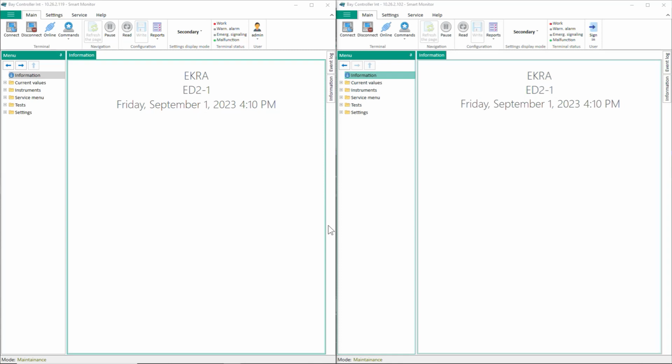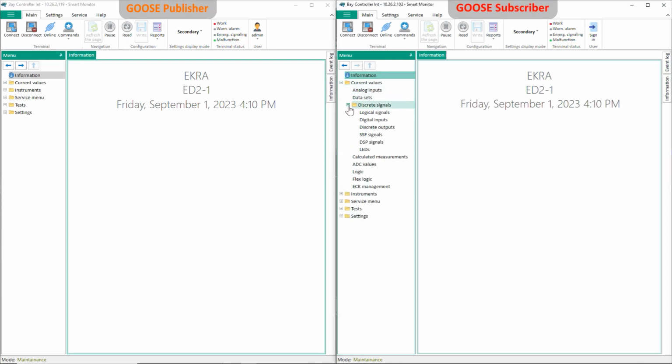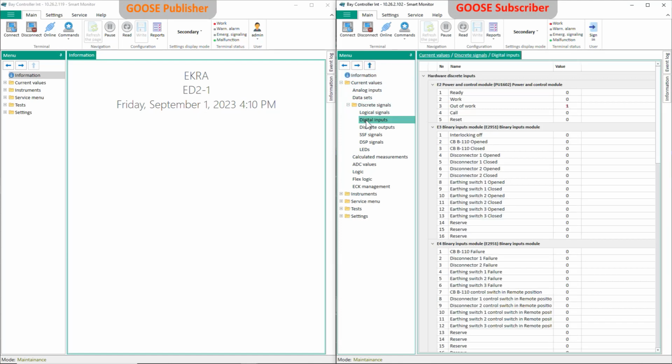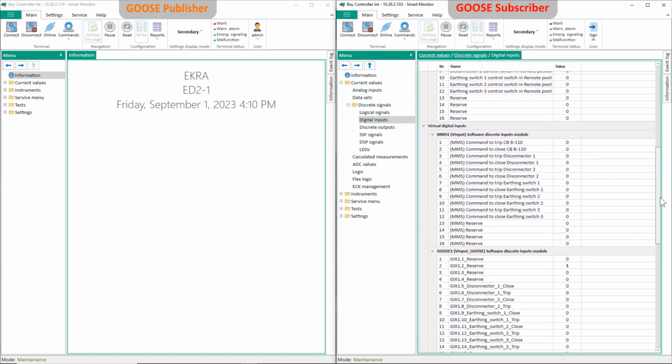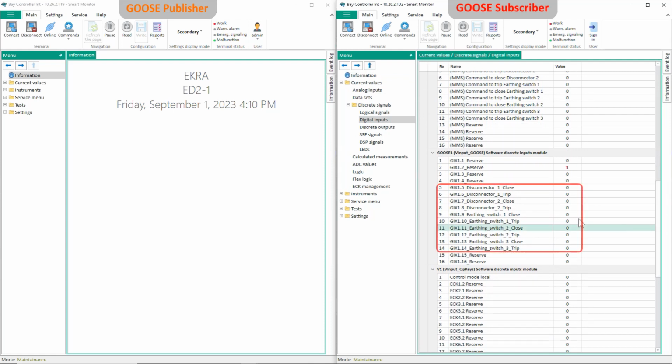To exclude the action of IED to the external circuits, we recommend switching the IED to the test mode. Find more information on that in the video tutorial checking of IED modules and functions in testing mode. The outgoing GOOSE message settings can be checked in two ways. The first way, check using the subscriber device, receiving GOOSE messages. The subscriber device must be in the same network with the publisher IED, configured to receive the checked GOOSE message, support the reception of test messages and show values of signals.